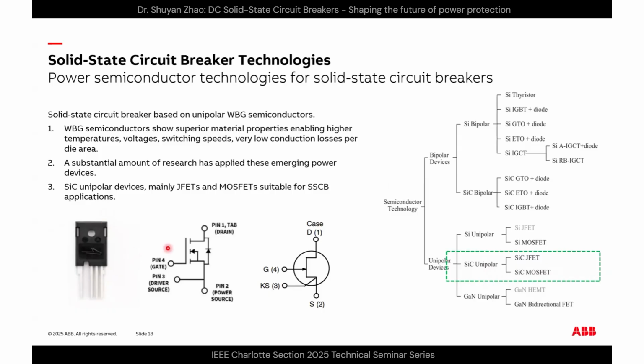Silicon carbide unipolar devices, mainly JFET or MOSFET, are suitable for SSCB applications. They don't need any supply, as they are normally-on devices. MOSFETs are also high voltage, but still need control power for the bias during on-state because they have a very low RDS-on, and they have relatively higher blocking voltage capability. Those two are especially suitable for solid state breaker applications among other unipolar wide bandgap devices.